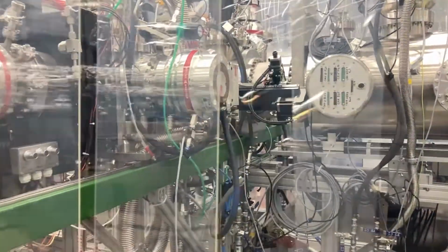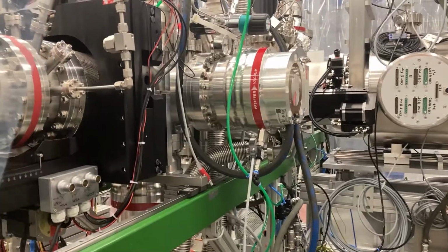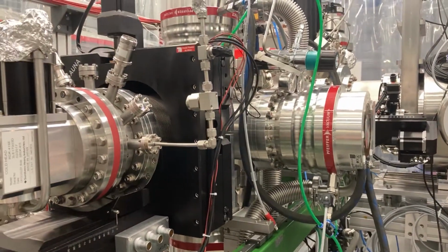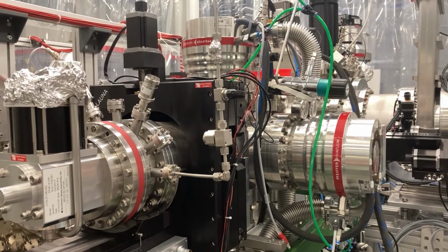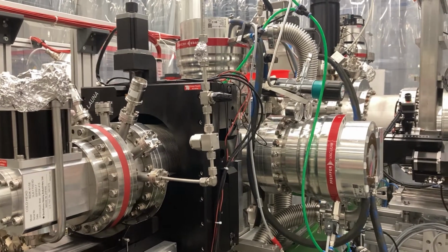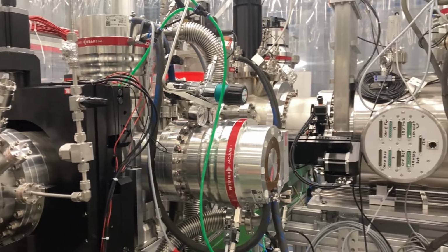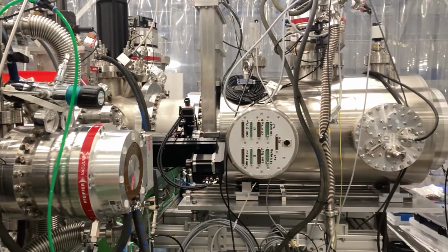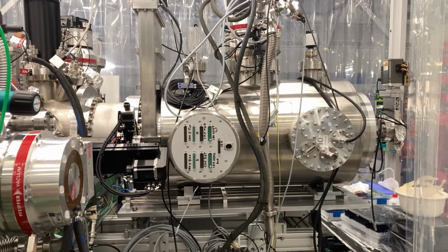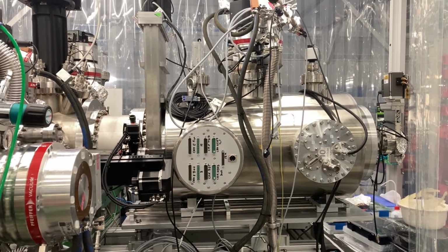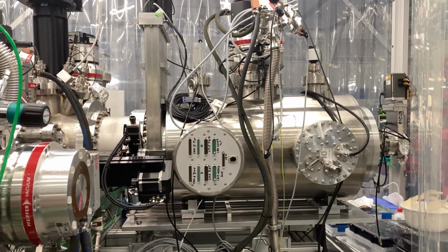The main components of this station are, first, the cluster source, which is on this side, a dedicated one to produce these larger systems. The second are some ion time-of-flight detectors, which are used, for example, to look for any fragmentation processes produced by the interaction with the FEL beam. The third and main component is an imaging detector. This is a 1 megapixel detector called pnCCD, which gives the information about the size and the structure of these particles. It is a dedicated detector optimized for the soft X-ray regime.